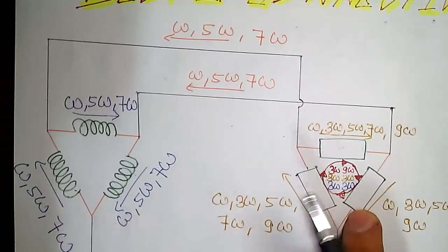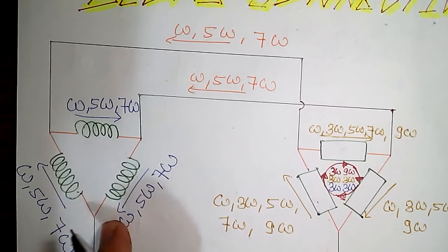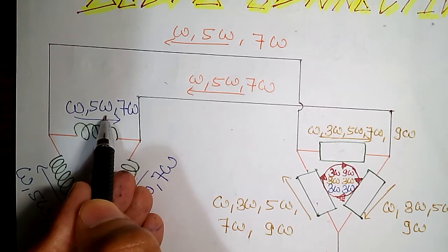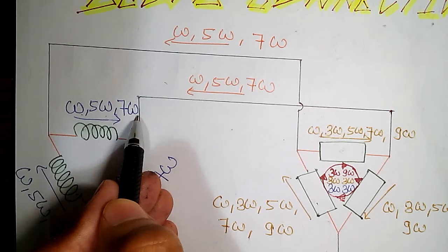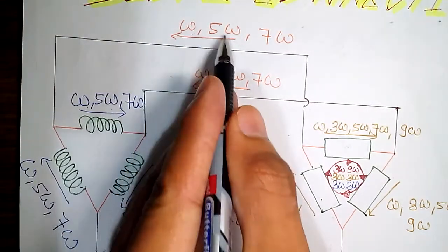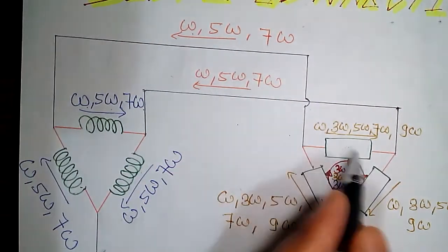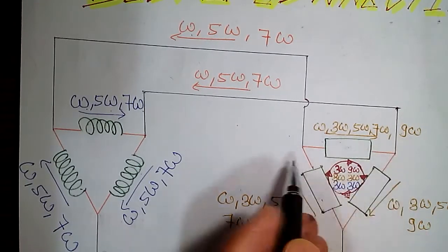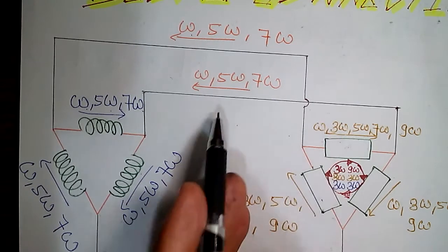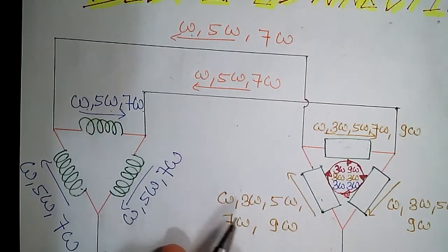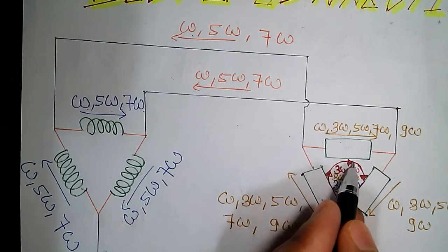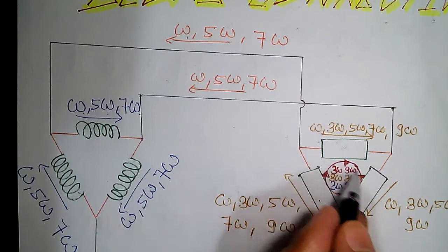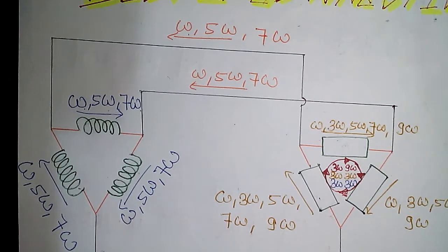First I have a drawing for you. This is my source and this is my load. What I am seeing in this drawing is that in my source I have Omega (fundamental harmonic), 5-Omega (fifth harmonic), and 7-Omega (seventh harmonic). Even in my line I have Omega, 5-Omega, and 7-Omega. But in my load I have Omega, 3-Omega, 5-Omega, 7-Omega, and 9-Omega — that is, in my load I also have triplen harmonics. But in my line and source I do not have those triplen harmonics. My triplen harmonics — third and ninth harmonics — are rotating in this circle only.